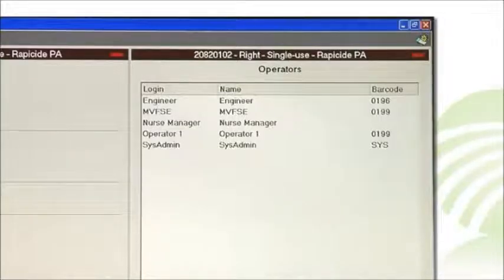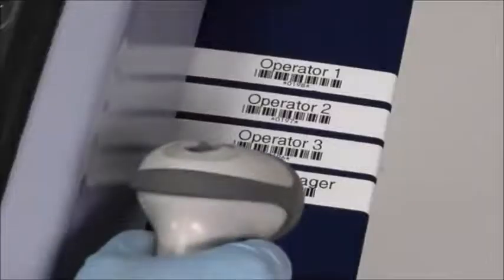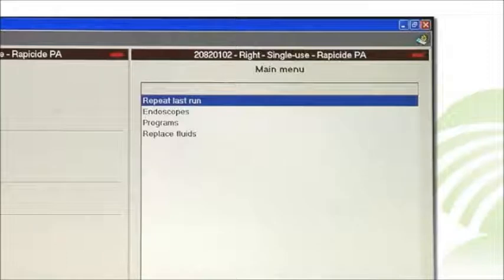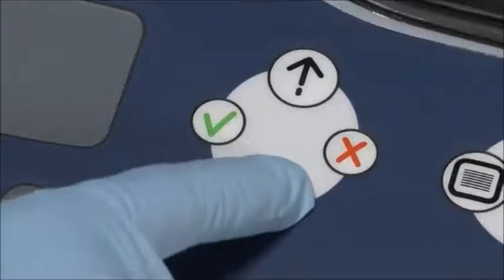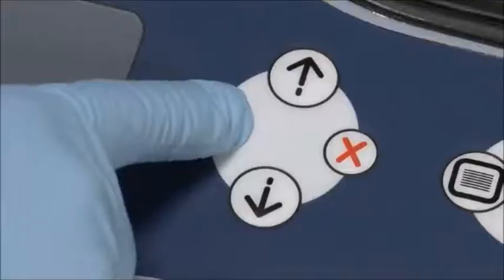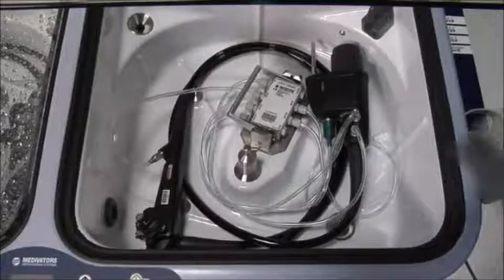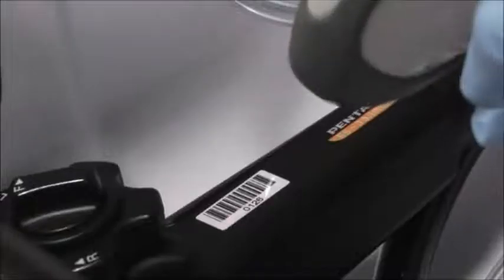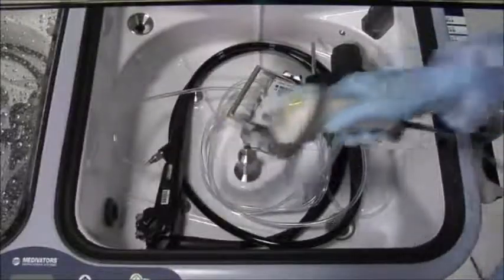The operator selection window opens. Use the barcode scanner to scan your operator ID barcode. The program selection window opens. Use the scroll down button to highlight endoscope selection and press Enter. Use the barcode scanner to scan the barcode found on the endoscope.